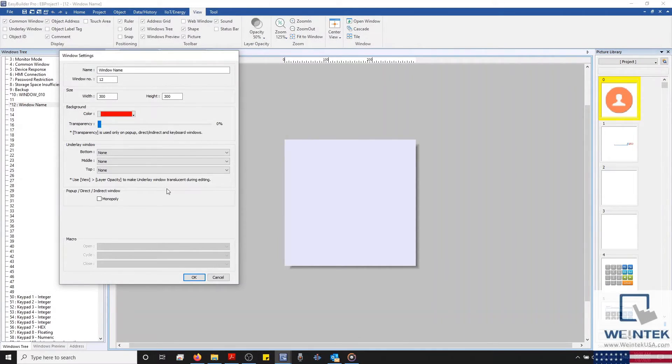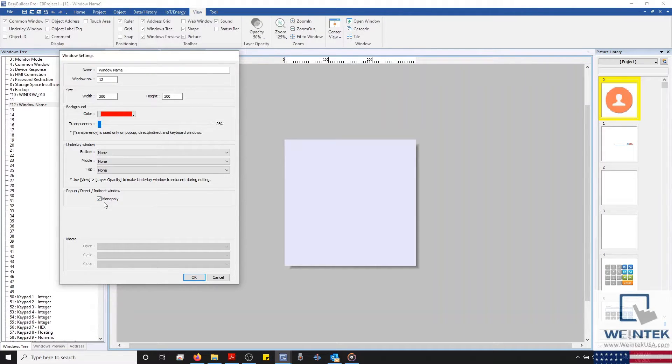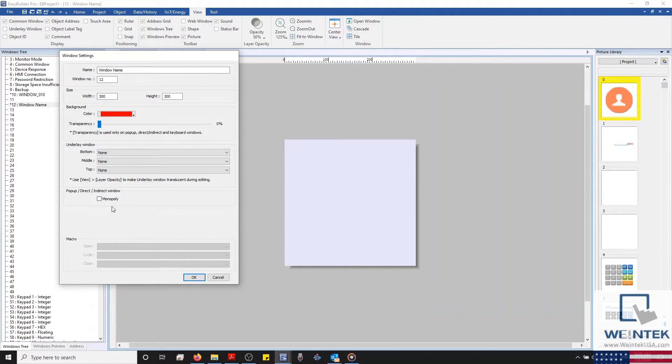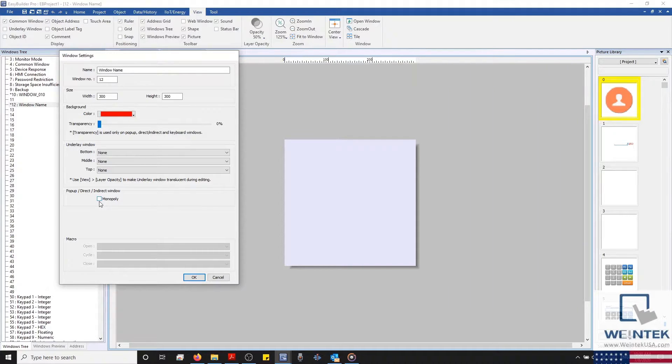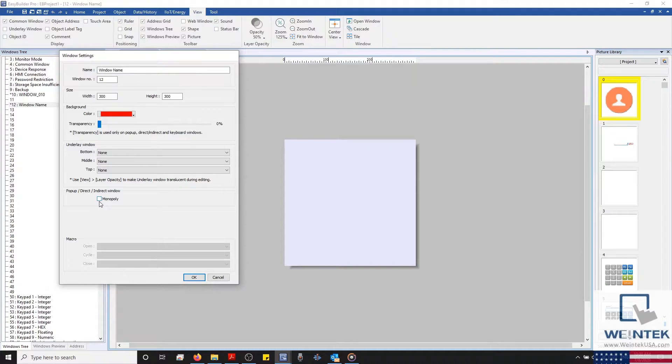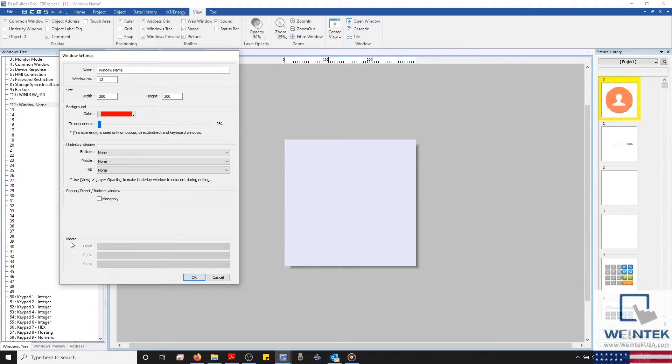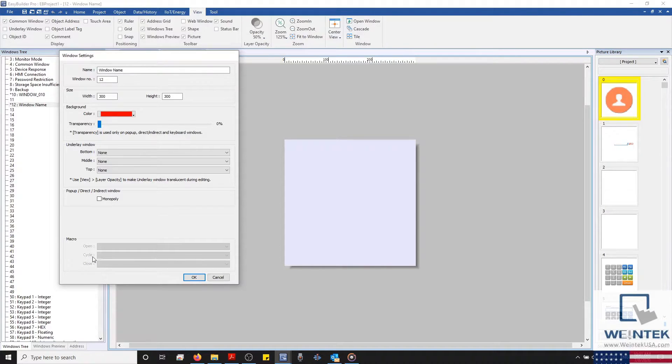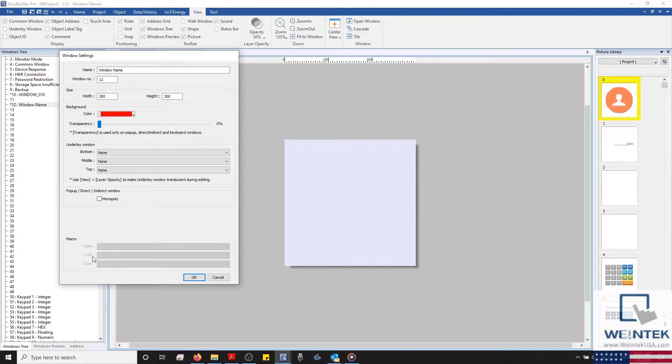Next, you'll notice the Monopoly button. The Monopoly button is used to give a pop-up or embedded window monopoly over the HMI screen, meaning that an operator will be forced to physically interact with that specific pop-up instead of moving it out of the way to work on what lies behind it. This feature might be used in combination with a system alarm or during system setup. And last but not least, we have our window-specific macro triggers. These can trigger a specific macro when the page opens or closes, or you can even configure a macro to cycle periodically every half second only when this page is open.